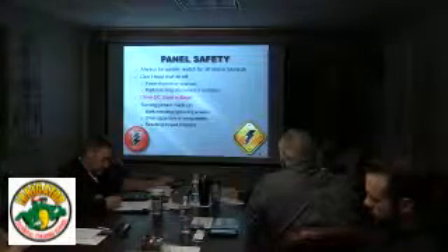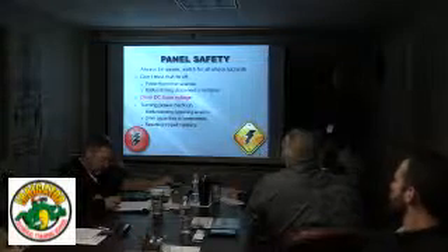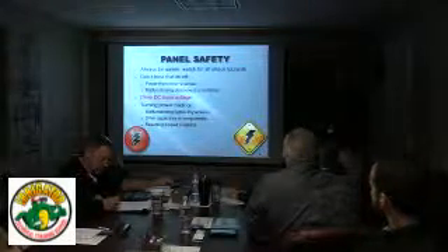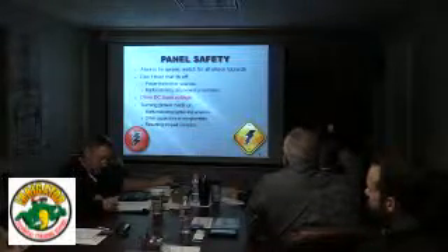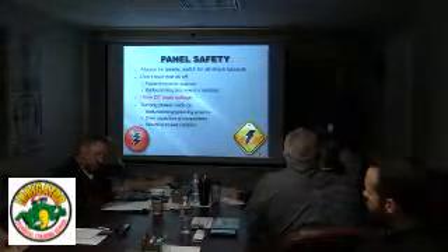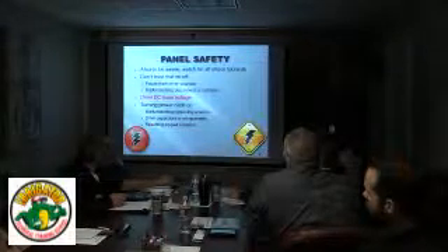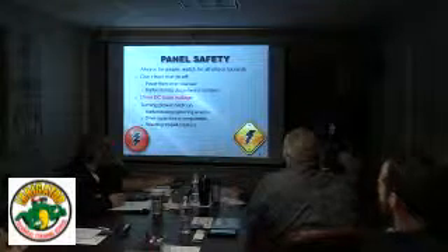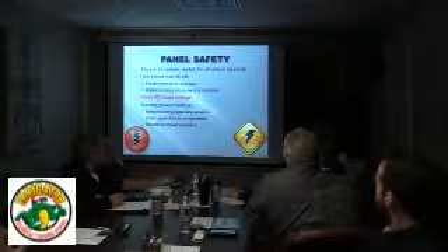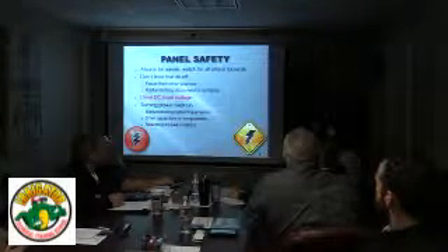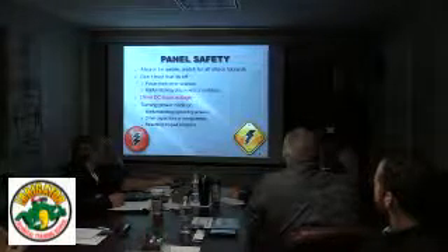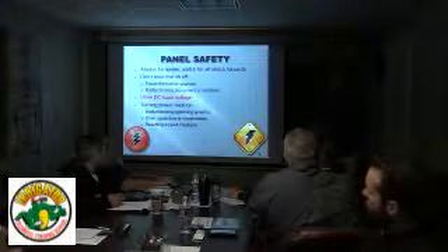I want to mention drive DC bus voltage. Many of you probably already know, but a drive stores its voltage on a DC bus capacitor bank in the drive. And when you turn power off to that drive, those capacitors stay charged. And depending on the drive type, the drive size, it could remain for several minutes. So just be aware of that.